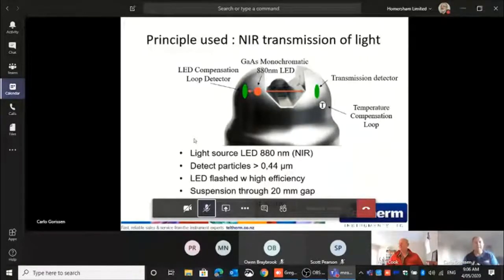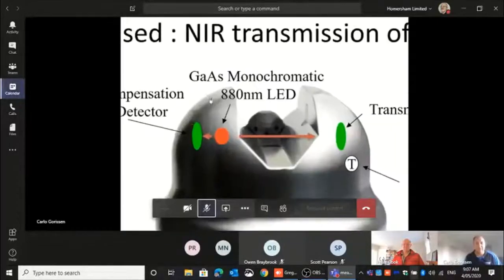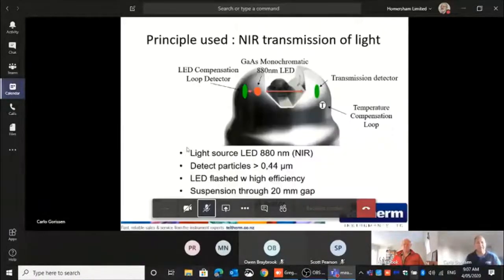The good thing with the unit is basically that we measure the strength of the LED as well, and we measure the temperature. So we compensate for both. Big gap in the middle, that is basically so we don't have big chunks of whatever get stuck between, because of course if that happens you have an issue. This little black dot you see here with the 3 little holes, I'll give you a close-up. This is basically the cleaning. So with high pressure up to 2 bar water or air, we spray it from those 3 little holes directly onto the lenses. So the cleaning is very effective with these units.